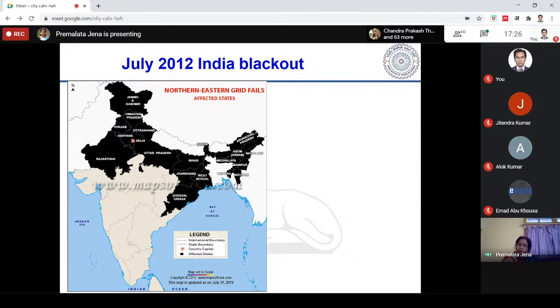In the July 2012 blackout, here's how it happened: there was a 400 kV double circuit line connecting two regions, carrying power from the western grid to the northern grid. Due to overdraw of power, one of the distance relay zone 3 units maloperated, a problem known as load encroachment.